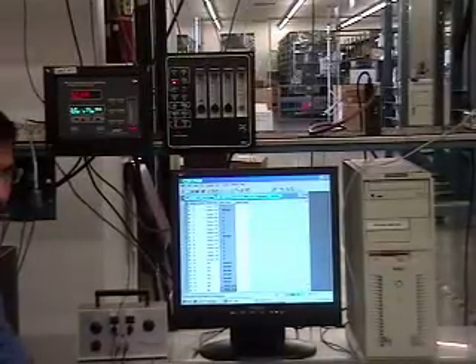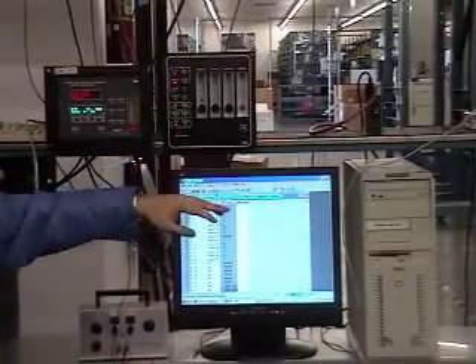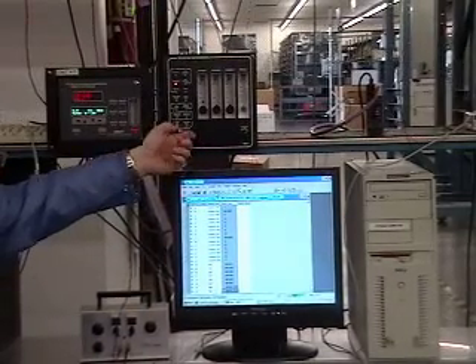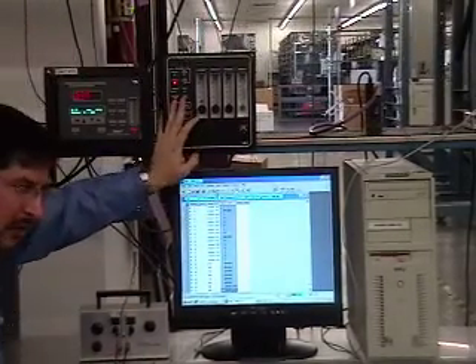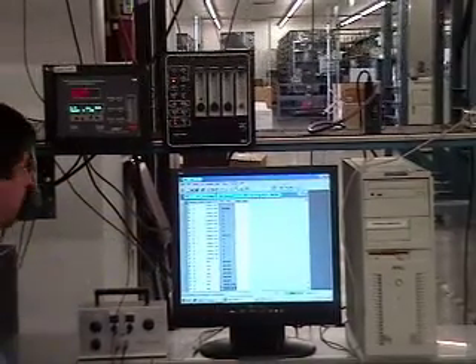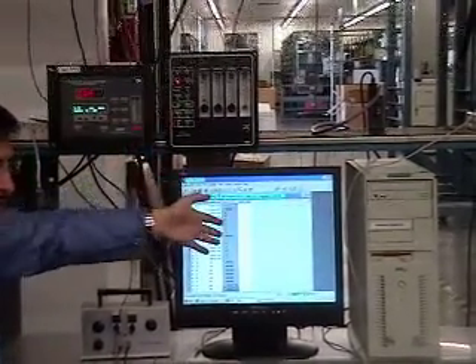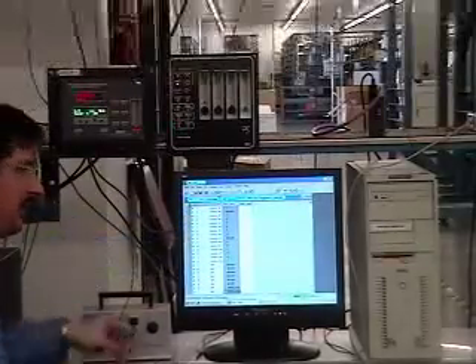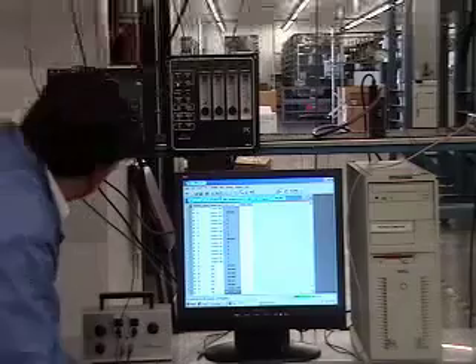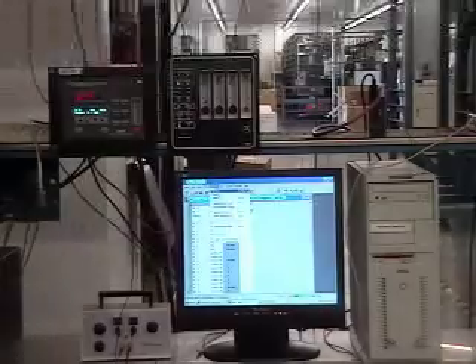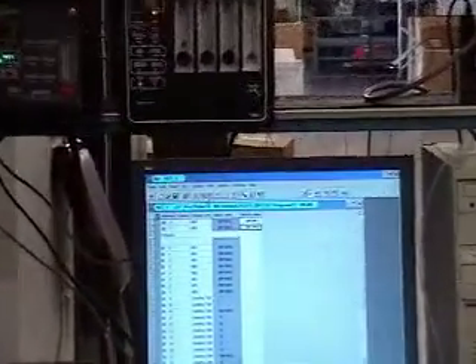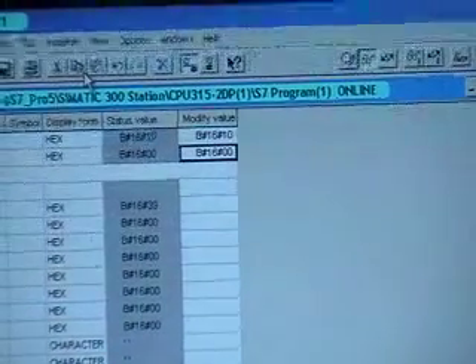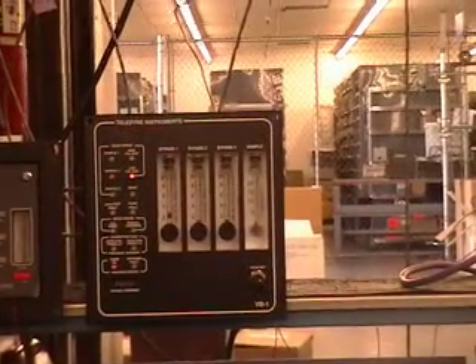Okay, so that's all there is. So I have all the commands, manual override still works, I can control manual override over here. Computer override still works. I can send commands from the Step 7, but if I send a command to open the 0 valve, the analyzer, of course, will not go to the 0. So let's do that. Send the command to 0. I can open up the valve, but because I don't have digital communication with the analyzer, it is still in analyzer mode. So I control the valves here, and that's why it's half digital.